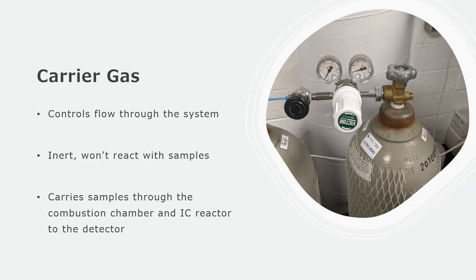The first thing that we'll talk about is the carrier gas. This is normally an inert gas used to carry the samples and push flow through the system. It carries our samples through the combustion chamber and the IC reactor into the detector. This picture on the right is what a typical carrier gas inlet looks like. Keep in mind you're going to need compressed gas cylinder training in order to operate one of these.